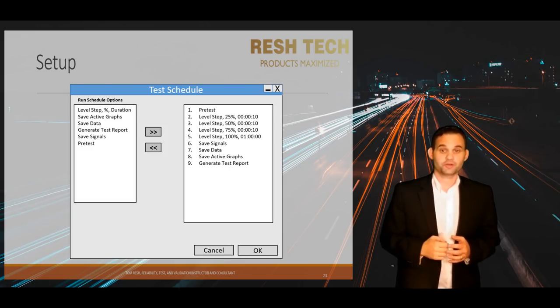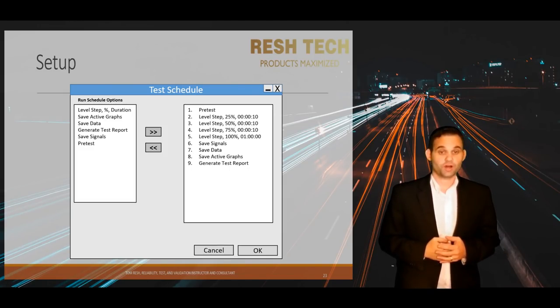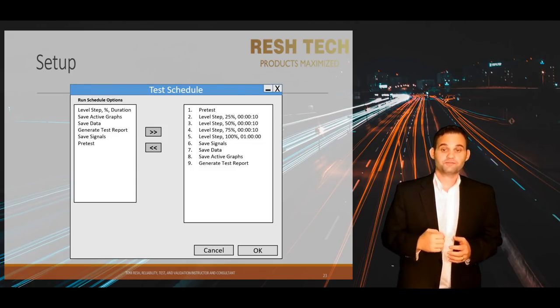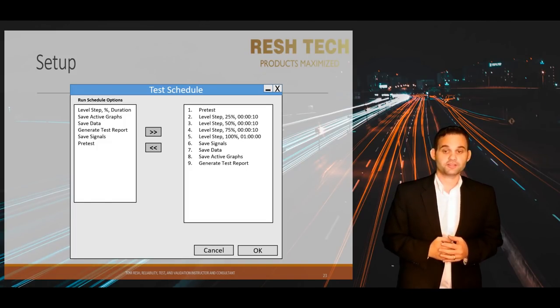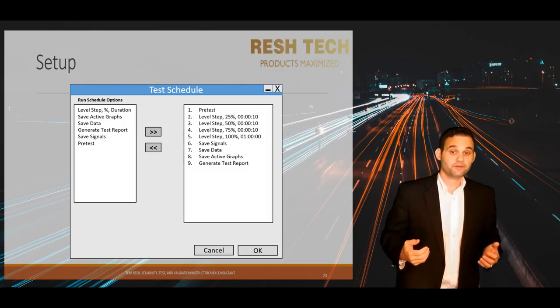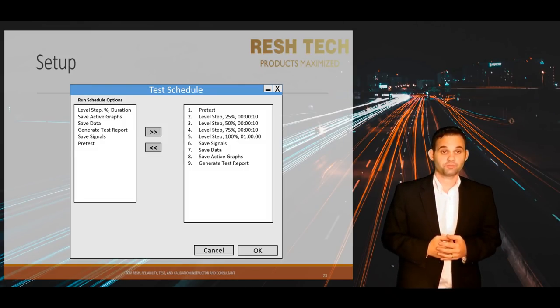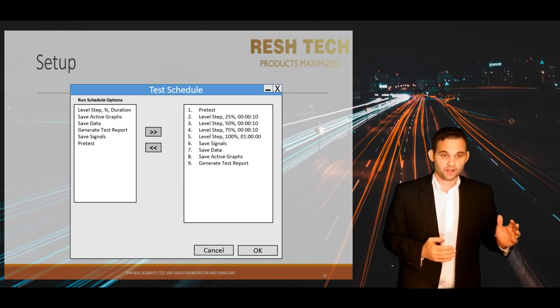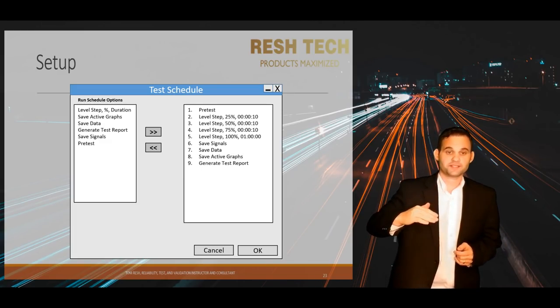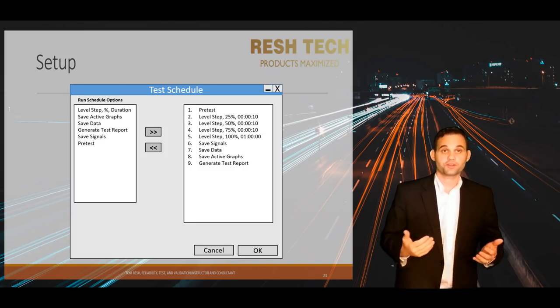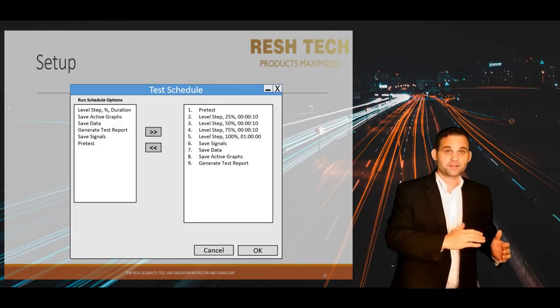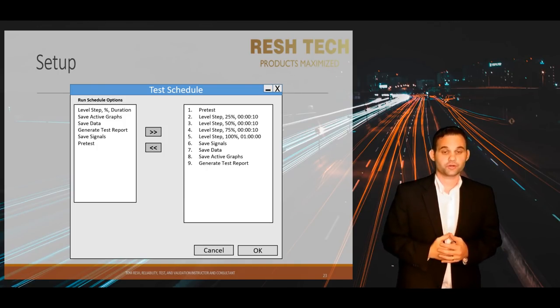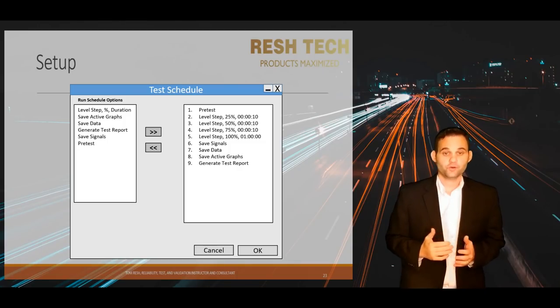Last but not least is your test profile schedule. In some vibration controllers, this is also where you put in your pre-test or ramp-up schedule. In this menu you will put the duration of your test. Most vibration controllers today also have options such as saving all signals displayed on your graph, screenshots, and auto-generating test reports. You will also want to add ramps at percentages until you get to 100% or the full level of your test profile, to gradually ramp up the shaker and not hit it with 100% drive right when you click start.